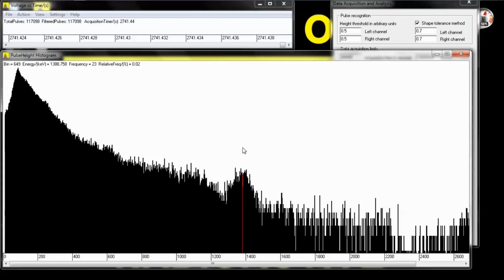In the logarithmic scale, you can get a better view of a few things. Now, the calibration is not dead on because at around 1388 kiloelectron volts, that actually should be 1461 kiloelectron volts, which would be potassium. This is a peak for potassium in the soil. The soil has potassium. And over here, that should be closer to 609, 610. You notice the calibration is a little bit better as you go down lower towards where we originally calibrated. And I'll go into details of calibration in another video, which explains why, for example, if I go over this direction, the calibration drops off. But that right there is a bismuth 214 peak.